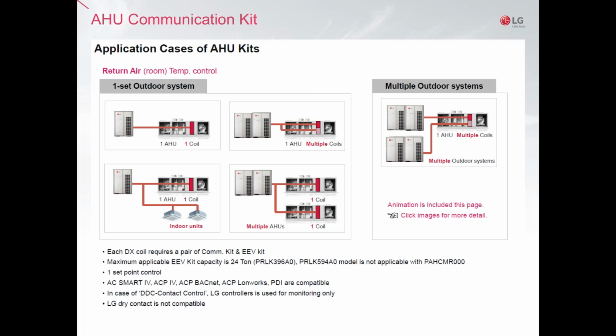If you need to go above 20 ton, you can also have a double module connected to a single coil or EEV kit. And in this case, the maximum capacity will be the maximum capacity of that single EEV kit. However, if you want even more capacity, in the case that you need a coil above the maximum capacity of the EV kits, you could also connect a VRF system to two or multiple coils. See the configuration in the top center. Or if you need even more, you can have two completely independent systems connected to two different coils in the same air handling unit, which we see in the top right.